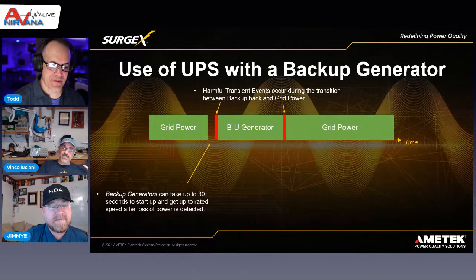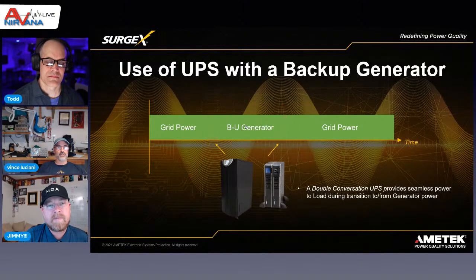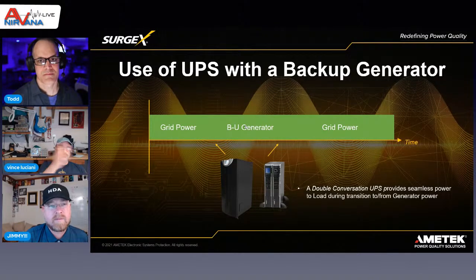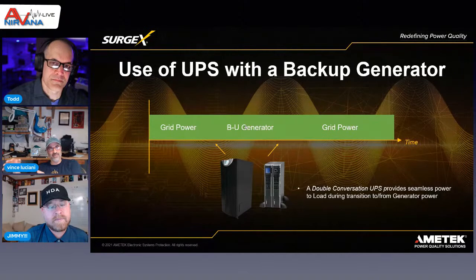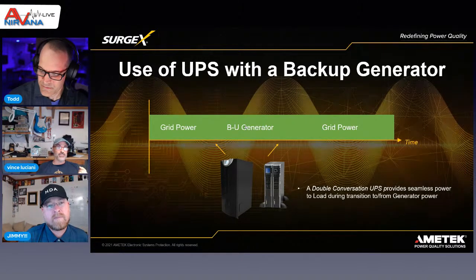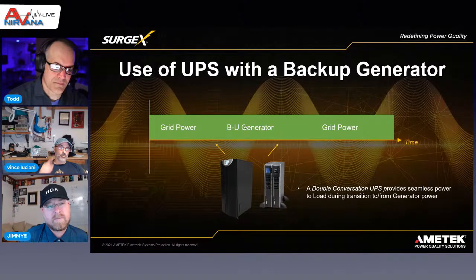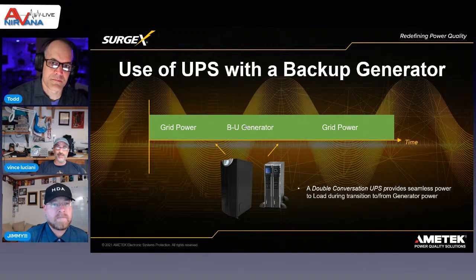When you team a double conversion online UPS up with a generator, it's the perfect solution, because you'll have an automatic transfer switch with the generator system that switches between grid power and backup power. You put the UPS downstream of that, so now we're conditioning the grid power, protecting during transition, keeping systems up and running during transition, and eliminating the surge event that's going on. It's really proven to be a necessity. Some integrators say, 'I got a generator, I don't need the UPS.' No—you need the UPS more than ever if you've got a generator.